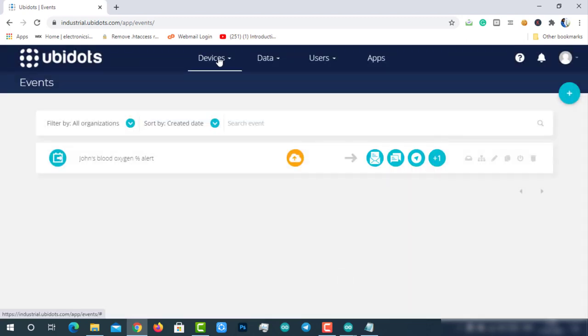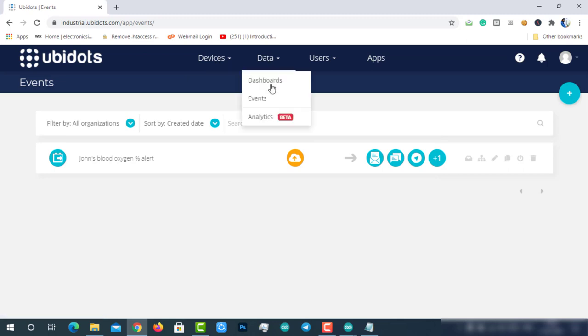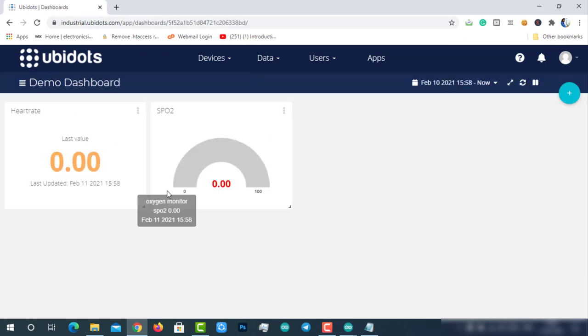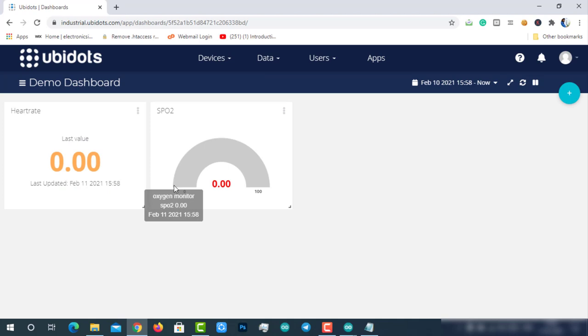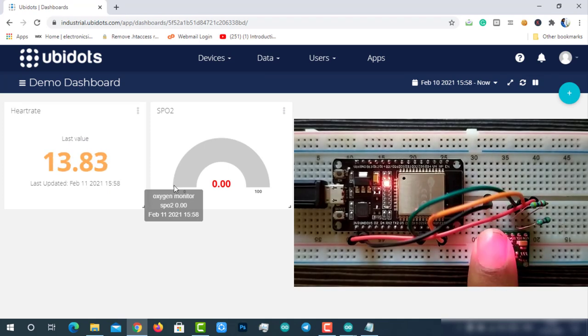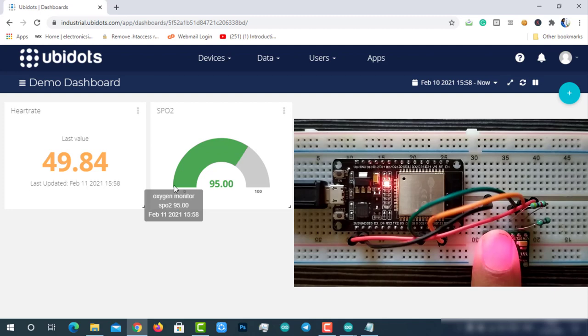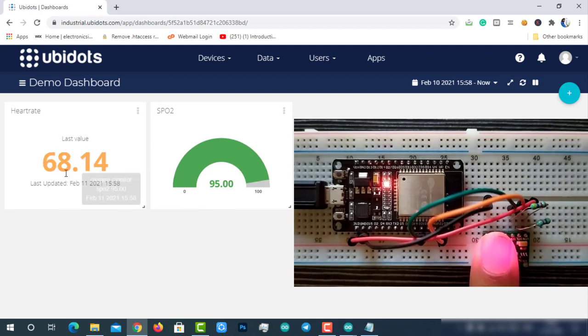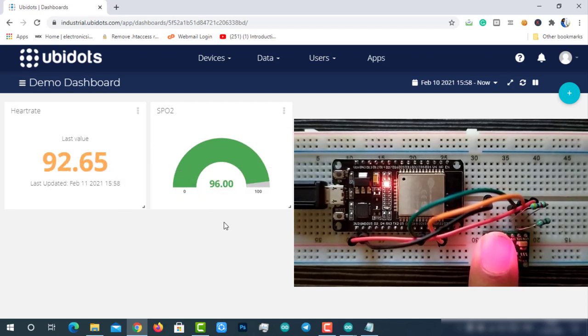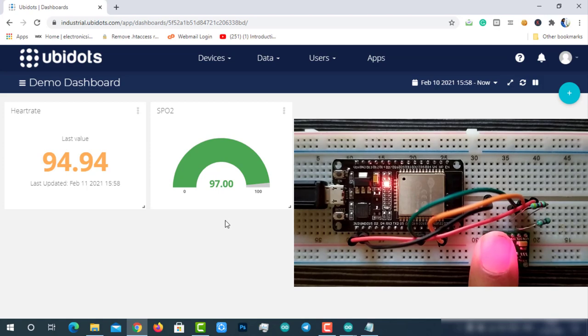So all these alerts are triggered when SPO2 value is less than or equal to 95% for one minute. Now it's time to test the back to normal alert feature. To make this SPO2 greater than 95%, I'm going to place my finger on top of the sensor. So it will send the exact readings of my body which will satisfy the event condition to trigger back to normal alert.